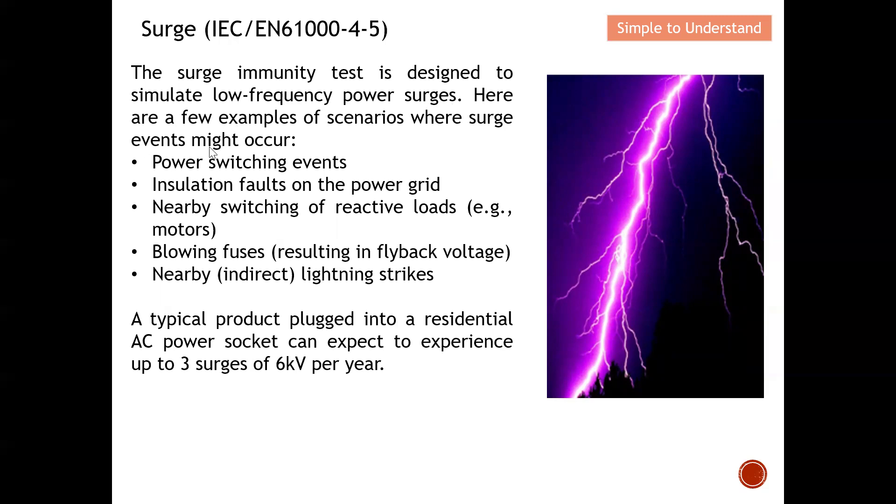Here are a few examples of scenarios where surge events might occur: power switching events when we switch from one power source to another, insulation faults on the power grid, nearby switching of reactive loads, fuses blowing nearby, and lightning strikes. A typical product plugged into a residential AC power socket can be expected to experience up to three surges of six kilovolts per year.